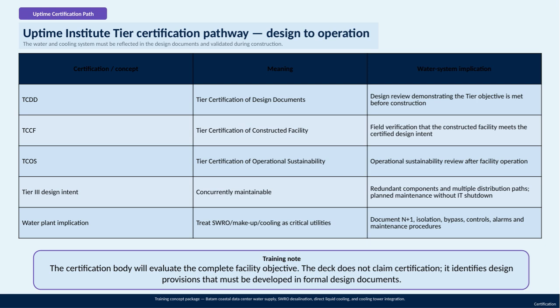This means it includes redundant components and multiple distribution paths, so that maintenance can happen without shutting down IT operations. Regarding the water systems, they must be treated as critical utilities. This involves documenting N+1 redundancy, isolation methods, bypass options, controls, alarms, and maintenance procedures to support reliable operation. One final note on training. The certification body looks at the entire facility objective as a whole.